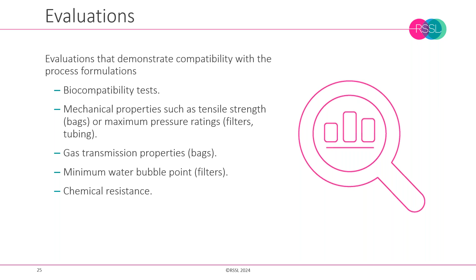We may need to understand gas transmission properties when we're talking about bags. We want to know that filters can be correctly integrity tested, and would have concerns about chemical resistance. We'd also need to extend these concerns to embrittlement. So if an item is going to be structurally damaged, and again, as something I said earlier, it could be initially at the first blast of radiation, or this could be something that happens over time. So we're establishing shelf life is quite important.